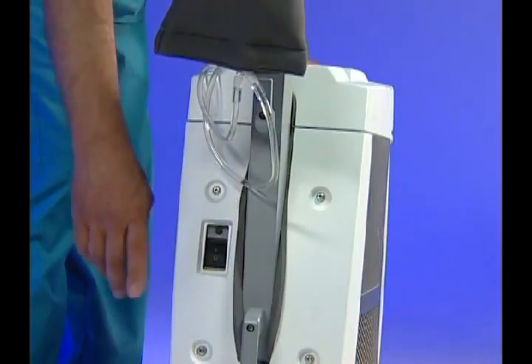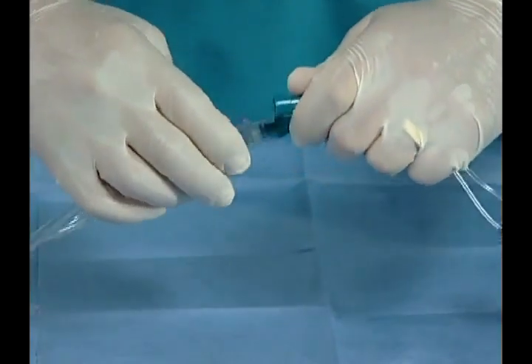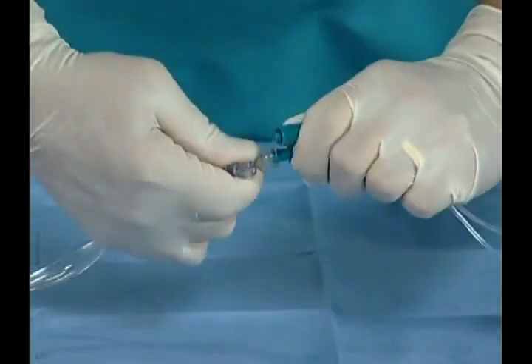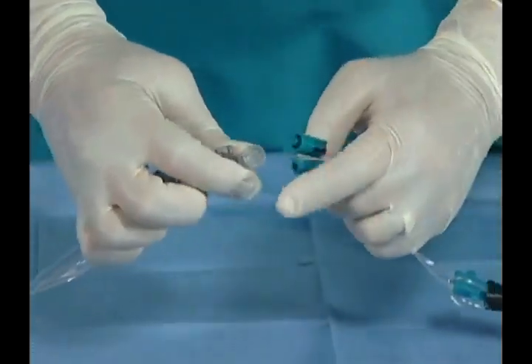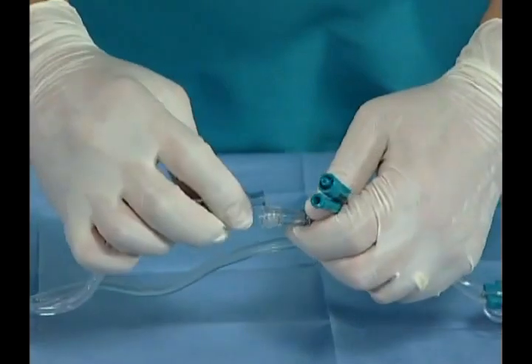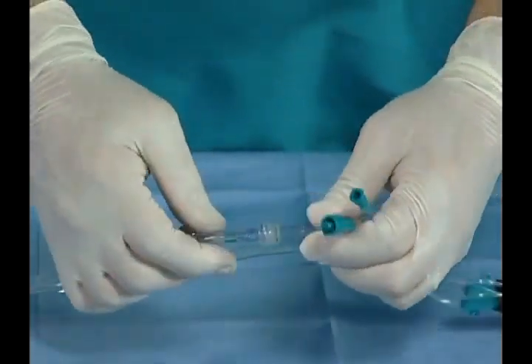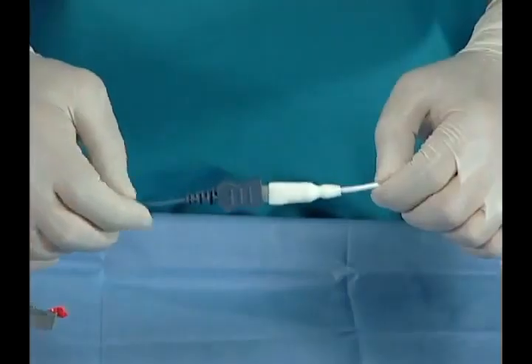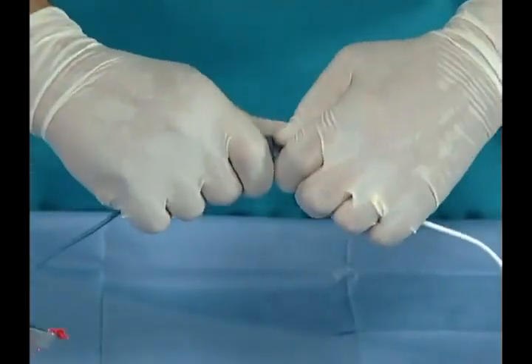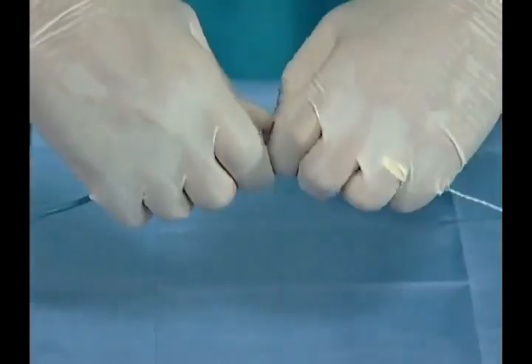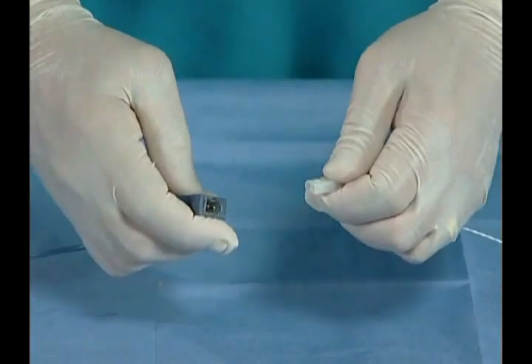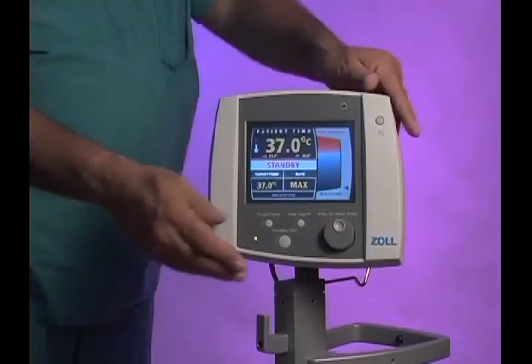After turning the power switch off, use aseptic technique to disconnect both tubing connectors from the catheter and connect the tubing set connectors to each other. Do not connect the catheter luer fittings to each other. Then, disconnect the primary and secondary patient temperature probes from the blue cables. The procedure is now completed.